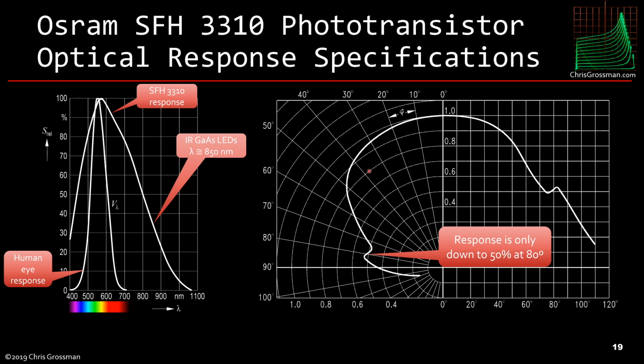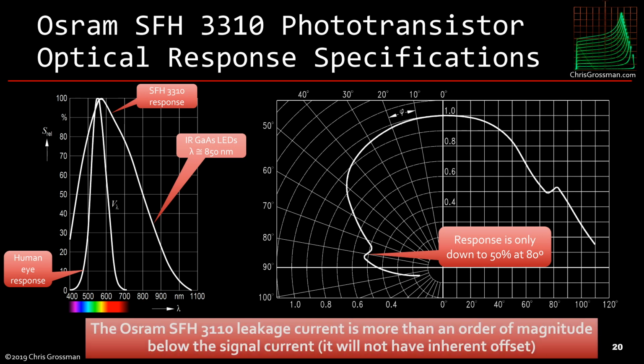So it's going to pick up a lot from the side, so it'll need to be shielded if we want it more directional. And the key thing about it is its leakage current is more than an order of magnitude below the signal current, so the photosensor itself will not generate inherent offset.